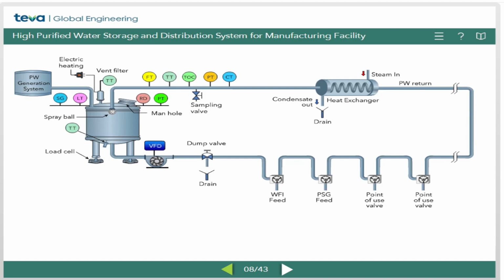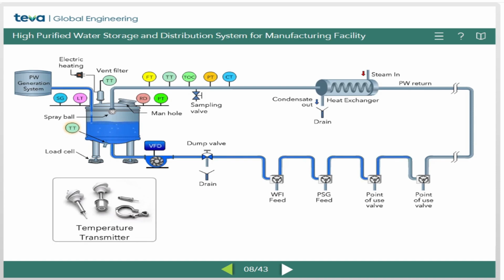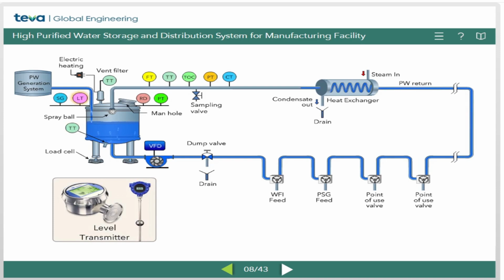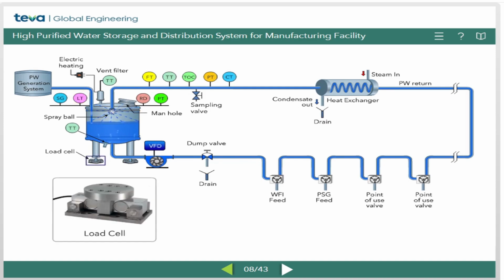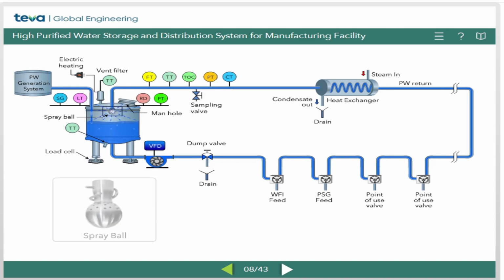Highly purified or purified water generated is fed to a storage tank, which is equipped with various instruments and components such as temperature transmitter to measure the temperature of water during sanitization, continuous level transmitter to indicate the level of water in the tank and to control the production of PW. Alternately, load cells or static pressure sensors can also be used for this purpose. Spray ball to ensure the unsubmerged surface of the tank is always sprayed with water to resist formation of biofilm.